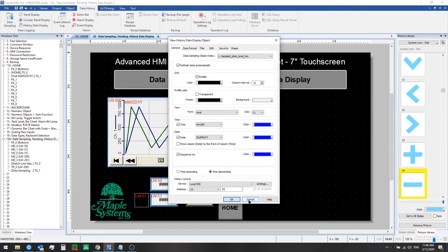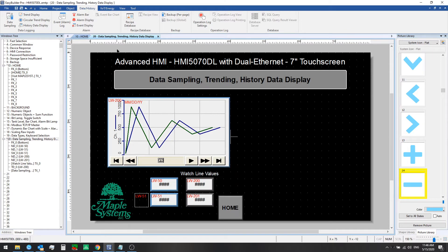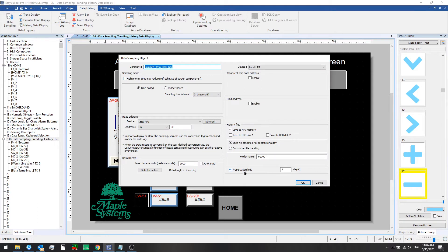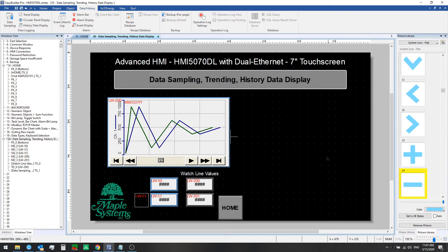Let's go back and look at how we set up the data sampling object in this project. Go to Data Sampling and click on this one. This one we set with a preservation limit of seven days, so we could only go back seven days in time to view the values from then in the history data display. We'll see in a moment how we can switch between days easily using a set word object.